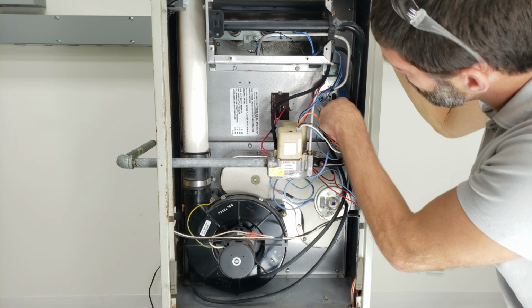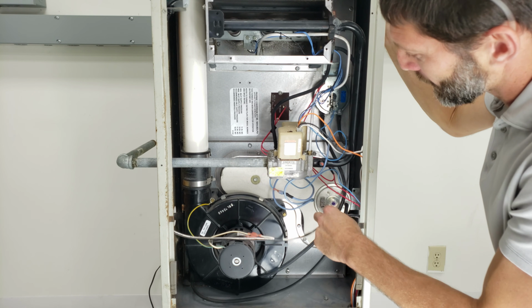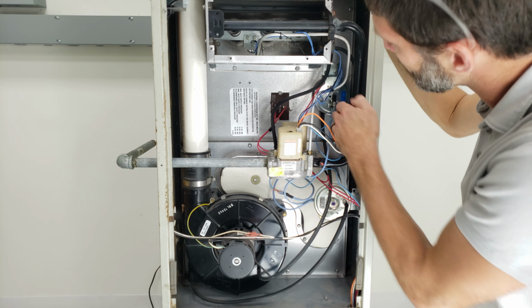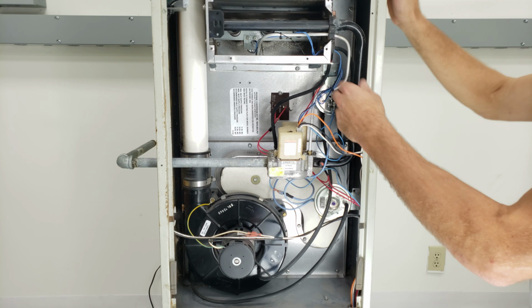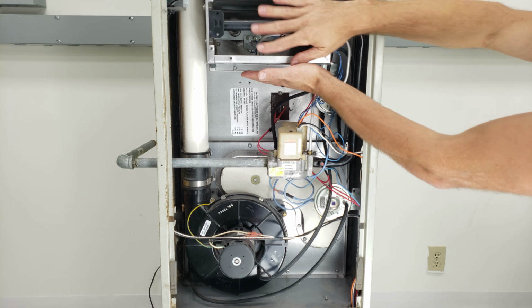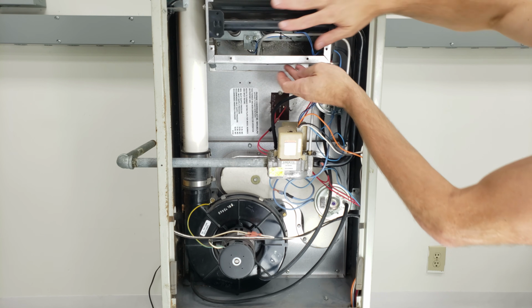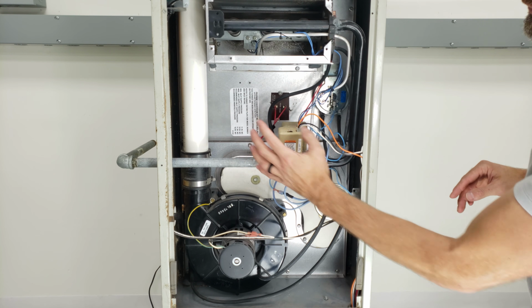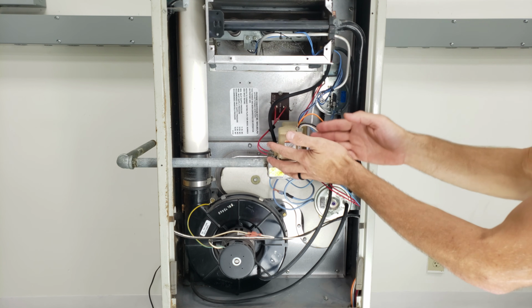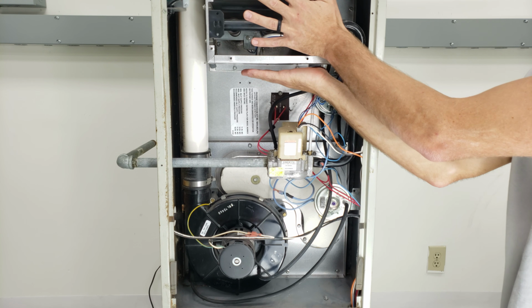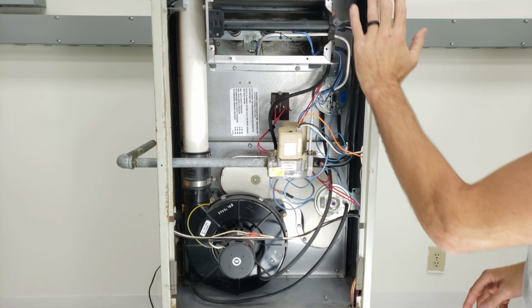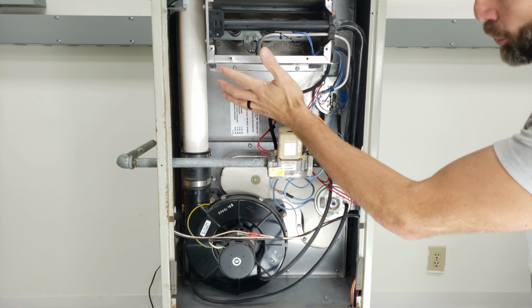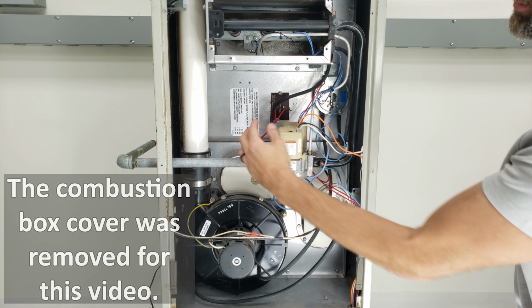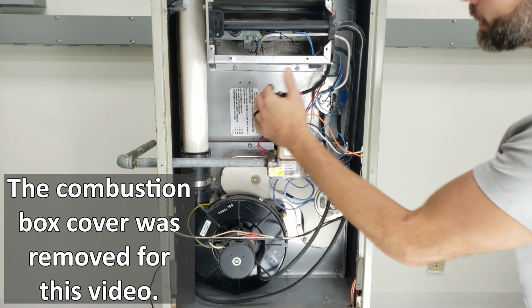Here we have our 2-port pressure switch, and one hose is connected right over to the inducer motor, and the second port right here is connected to this sealed combustion box. So anytime you have a sealed combustion box, you also have a T with a tube going over to the gas valve so that the gas valve has the pressure that's within this box. If there was no combustion box and this was just open, then you wouldn't need a tube right here, and it would just be reading the atmospheric pressure.